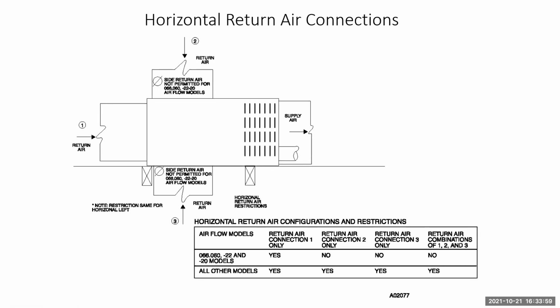Read your installation manual. This is in there anytime. Your installation manual should be read every time you put a furnace in, but we all know that doesn't always happen. But when you're doing horizontal especially, pay attention to this, please. Because if you do this improperly, you will be calling this because things are not going to be running right. And nothing's going to tick you off more than having to go back there and rework duct. So read it and do it right the first time, guys.